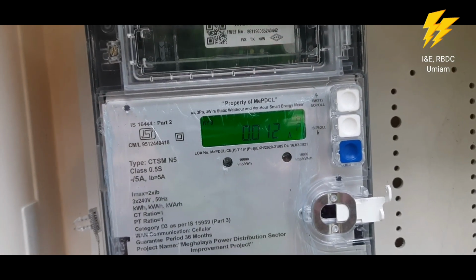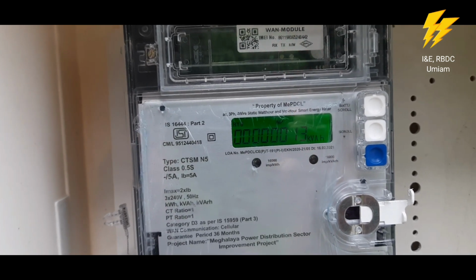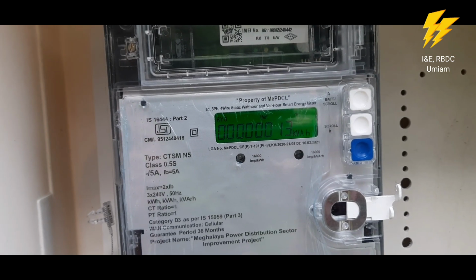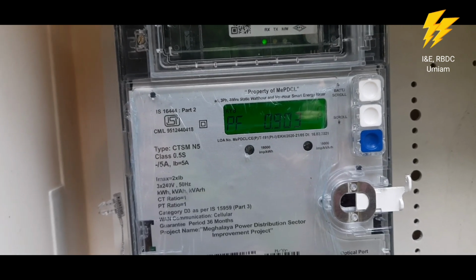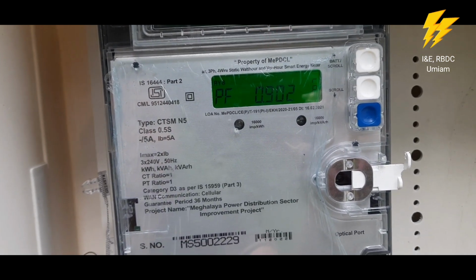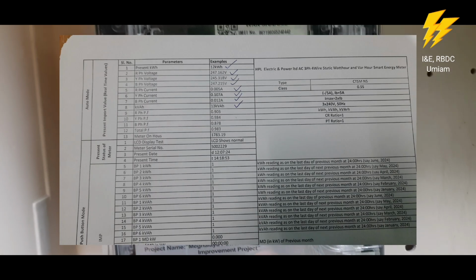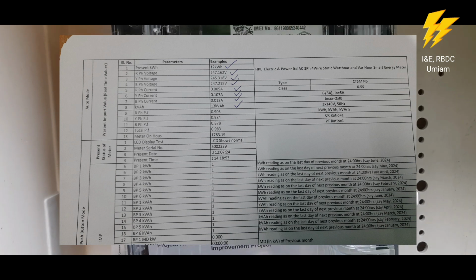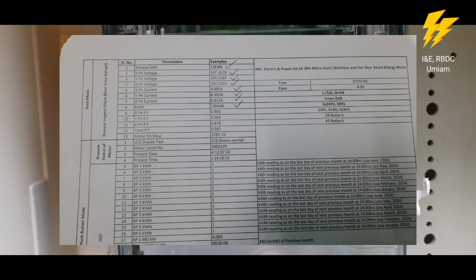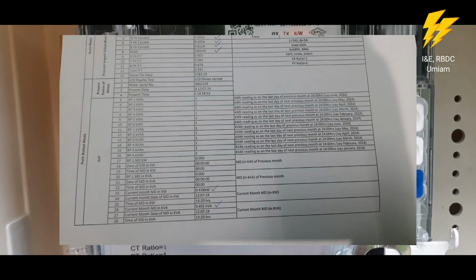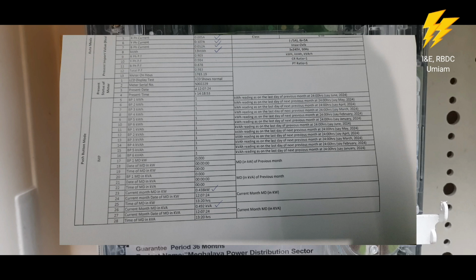Before we proceed further, just to remind you that the reading of this can be taken in two modes. One is the auto mode and the other is the push button mode, where you have to keep pressing the button. The required parameters are in auto mode only, which shows the present import values in real time, and these values are sufficient for you to bill the consumer. But sometimes, if you want the current month's maximum demand, then we can use the push button mode.